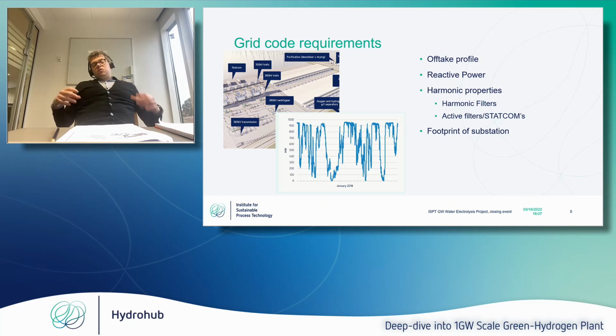You can, to some extent, mitigate this by choosing one power conversion technology or another. But if that's not sufficient, you need to add other passive harmonic filters, shunt reactors, or ultimately active filters or STATCOMs, to obtain the harmonic performance that the grid operator, in this case Tennet, will accept, since we will push harmonics into the grid.